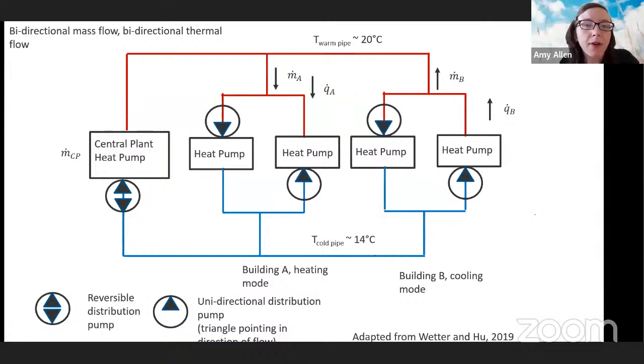And in this example, the delta T across each connected building is controlled to around 6 degrees C, with the warm pipe operating in the range of 20 degrees C and the cool pipe operating in the range of 14 degrees C. And in systems of this nature, there's often a range of acceptable temperatures on each pipe or in the network as a whole. And shown here are water source heat pumps conditioning the building, and also circulation pumps drawing water from either the warm pipe or the cool pipe, depending on the load conditions at the building.